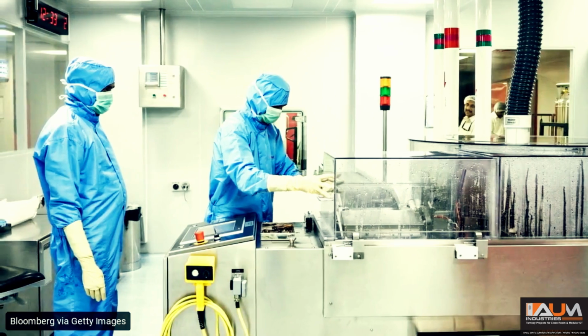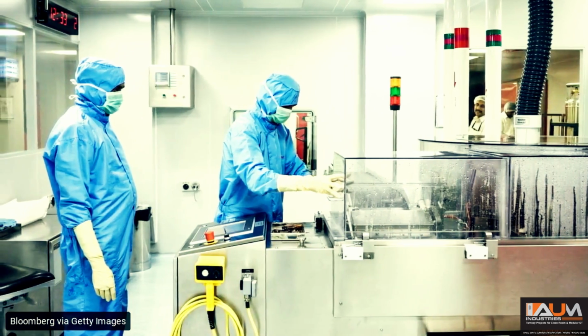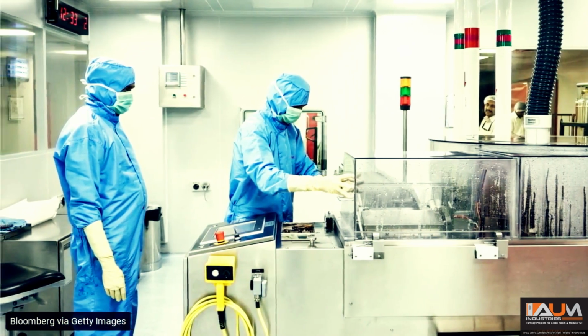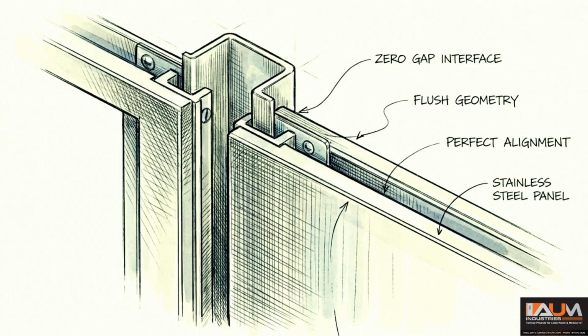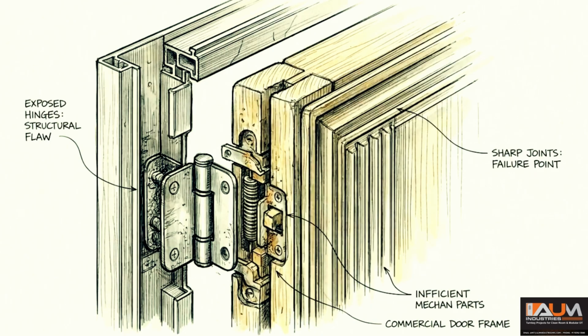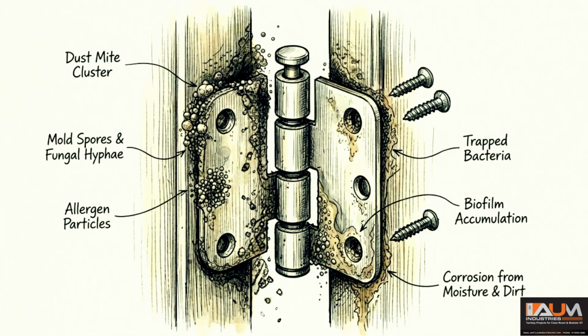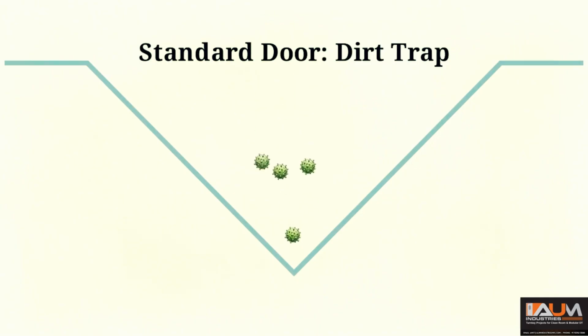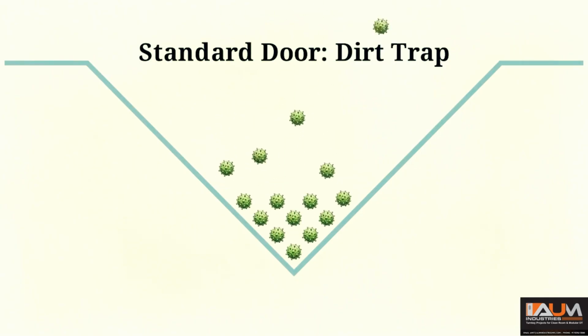If you look closely at the machinery in a highly controlled laboratory or pharmaceutical cleanroom, you start to understand the extreme material standards required for the physical surfaces themselves. In commercial buildings, architects love decorative profiles, sharp grooves, and standard exposed metal hinges. In a hospital, those exact design features are active biological threats. Take a microscopic look at a standard door hinge or a textured groove. Over time, dust, pathogens, and microscopic particles naturally settle deep inside those sharp 90-degree corners.